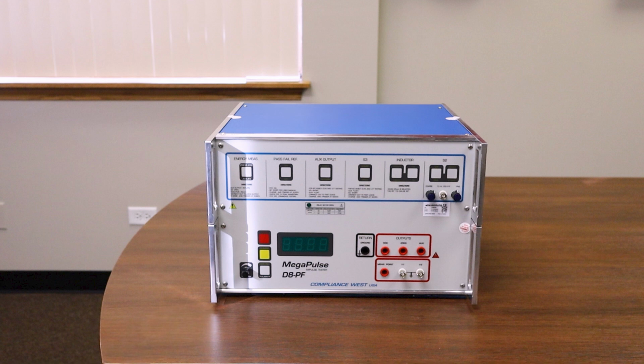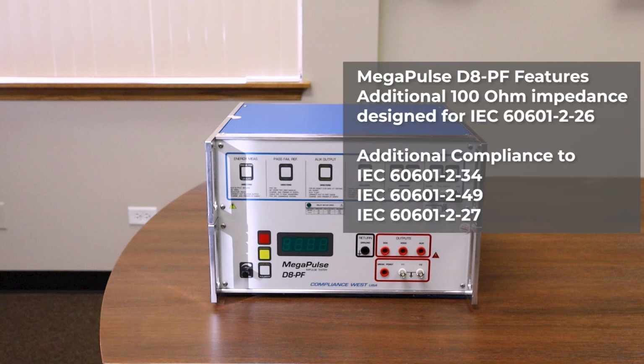The MegaPulse D8-PF is the newest version of the MegaPulse series designed for defibrillation-proof testing. The D8-PF includes a few modifications to the older D5-PF, including the addition of another 100 ohm impedance designed for compliance to the newest version of IEC 60601-2-26, figure 201.101.